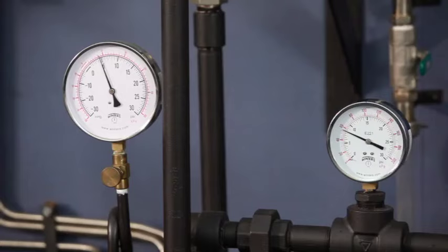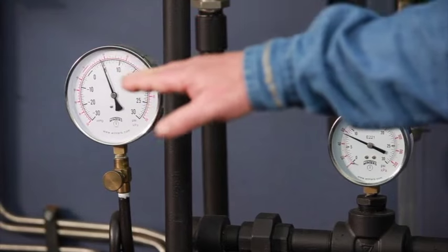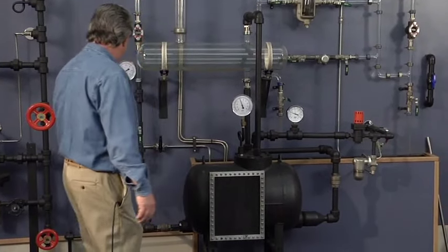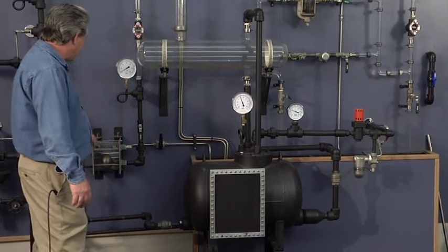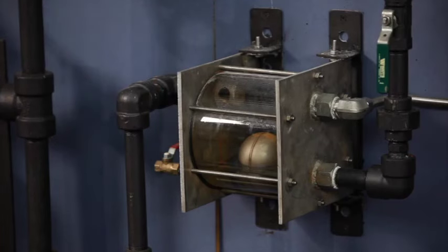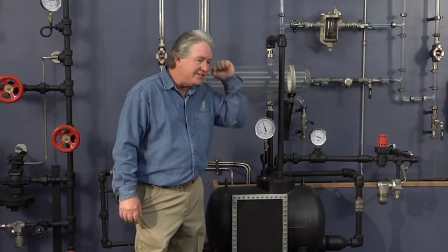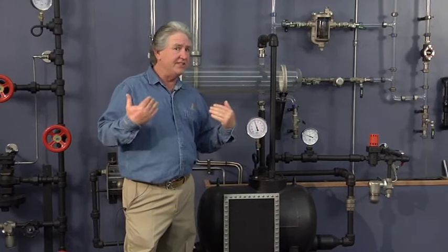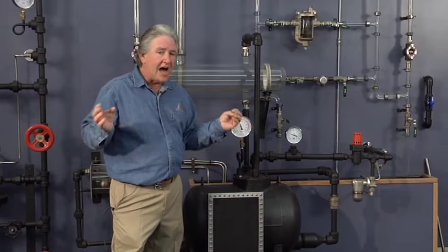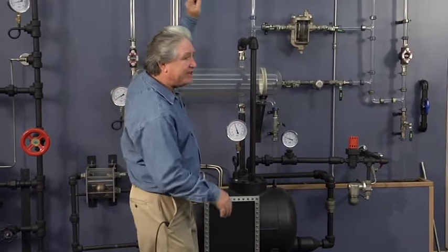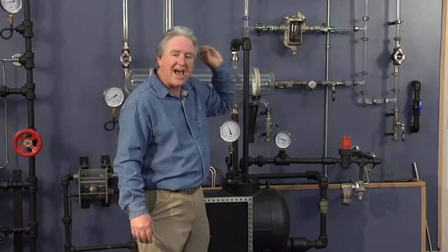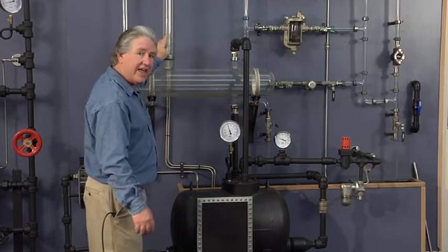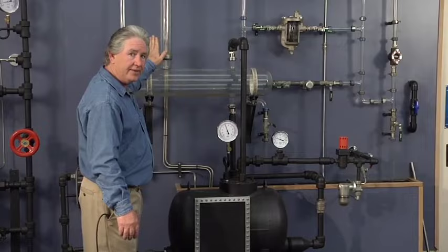Right now, you'll see the outlet pressure of the exchanger is at 5 pounds, like it has been. No different. We have 5 pounds coming in, we have 5 pounds coming around, and we have 5 pounds that should be coming right to the steam trap, okay? And remember this is critical. It's a common mistake that even some seasoned veterans make. I don't care what pressure you feed that exchanger. What matters to us is what's on the outlet of that exchanger, okay?